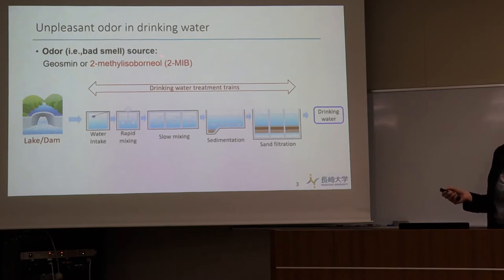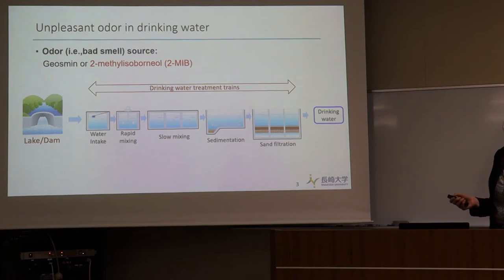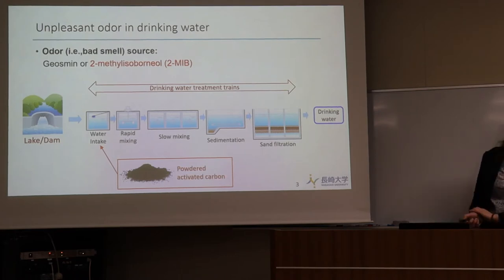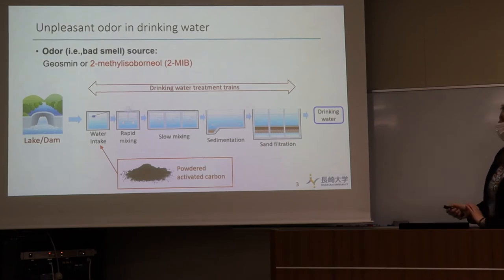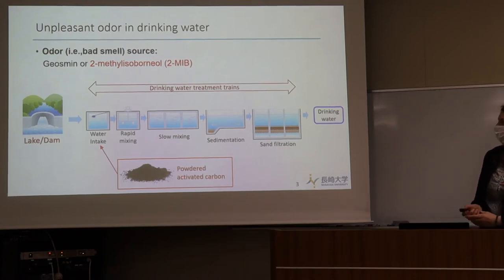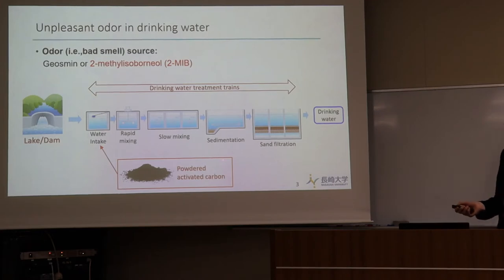The odor is usually coming from two compounds, geosmin and 2-MIB, that are produced by algae. Algae usually grow fast during spring and summer, so it's quite a seasonal problem. The way to address this is to add activated carbon at the water intake. However, activated carbon is quite expensive and you need to use the right dose. Another option is to use ozone as a year-round odor removal treatment, but it's quite expensive and not available everywhere.